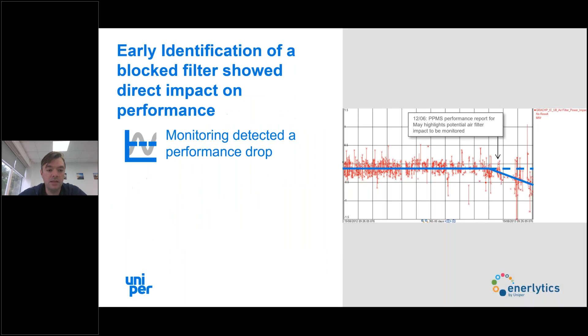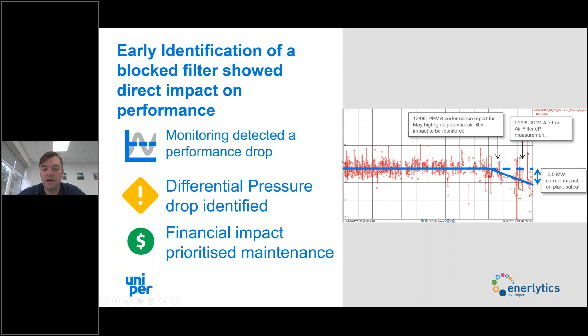The second case study is on the air inlet. So this is on GT. You can see here on 12 months of data, we've detected a drop in performance, where at this point we don't know why. Then 6 weeks later, because the unit had advanced condition monitoring, we picked up a change in differential pressure. So those two things together tell us that that is a blocked filter, or the beginnings of a blocked filter. But importantly, we could say how much is being lost. So it was okay for the unit to take another couple of weeks, losing 0.5 megawatt, rather than take an unplanned outage and lose out on the revenue and the fines from the regulator. So it gives them financially prioritized information.